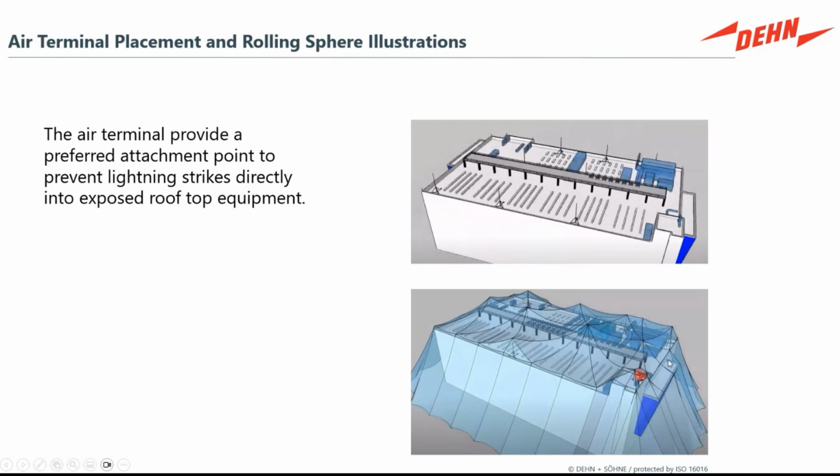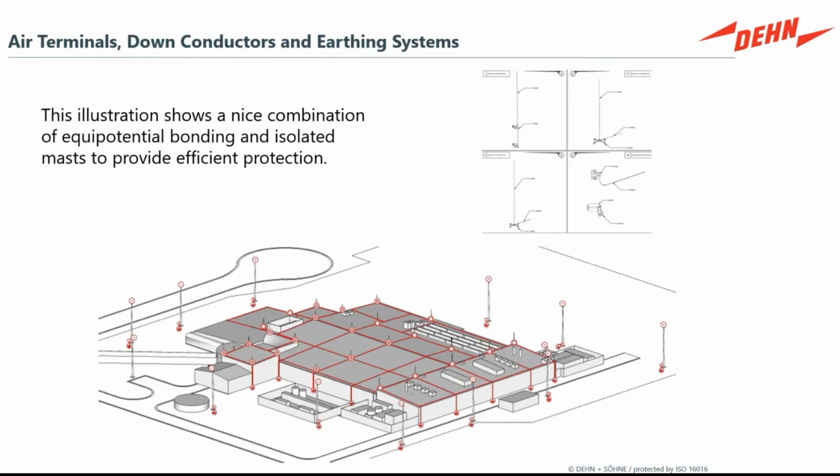And you may also need to take into consideration things like the lamp poles out in the parking lot. These are now inducing lightning strikes into the lamp, into the luminaire, directly into your electrical circuits. Now you've brought the lightning directly into your electrical service panels from the outside through the light pole. And this is where the application of proper air terminals on the light poles, surge protection at the luminaires would reduce the energy that's brought back in through the back door, as it might look.